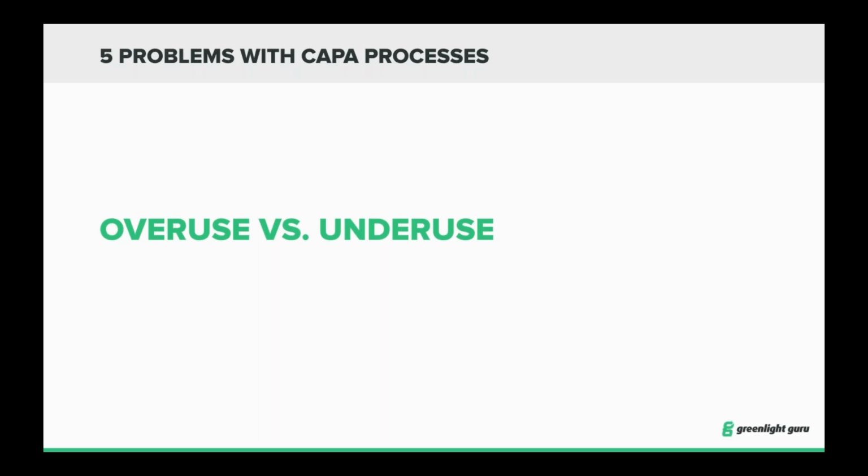I'll talk a little bit more about the quality system relationship with CAPA here in a little bit. Root cause, man, this is a really big challenge, I think, for many in the medical device industry: getting to the root cause. And the challenge with respect to CAPA is a lot of times what people will do when documenting their root cause is they will almost regurgitate or restate the problem statement rather than drill down to find the specific root cause.